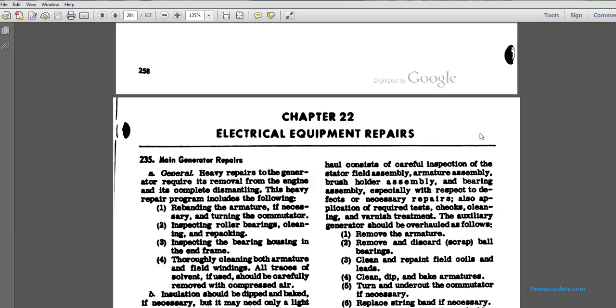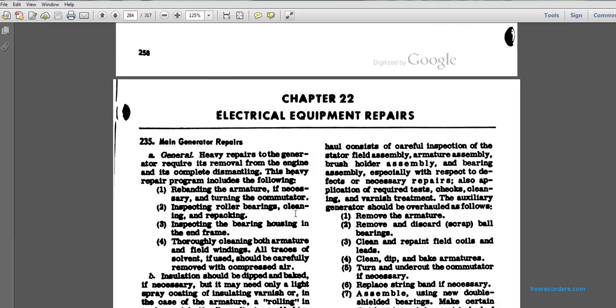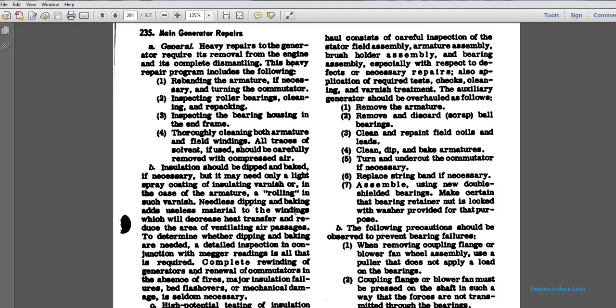windings, and all traces of solvent should be carefully removed with compressed air. Insulation should be dipped and baked, and if necessary, may be needed only in a light spray coating of insulation varnishing. And in the case of the armature or winding, such varnishing needs the dipping and the baking, and adds a less useless material to the winding, which decreases the heat in the transfer, reducing the air to the ventilation.